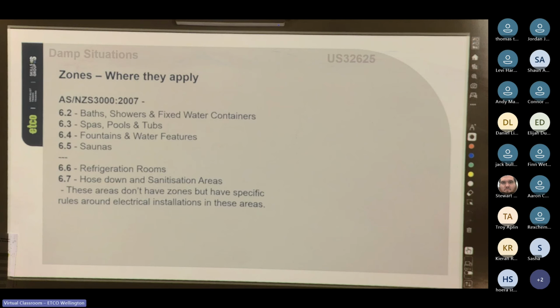So according to AS/NZS 3000, 2007, in section 6, which is damp situations, we have 6.2, which covers baths, showers, and fixed water containers. 6.3 is spas, pools, and tubs. 6.4 is fountains and water features. 6.5 is saunas. 6.6 is refrigeration rooms. And 6.7 is hose down and sanitation areas. These areas don't have zones. We'll talk about those in a little bit, but have specific rules around electrical installations in these areas.